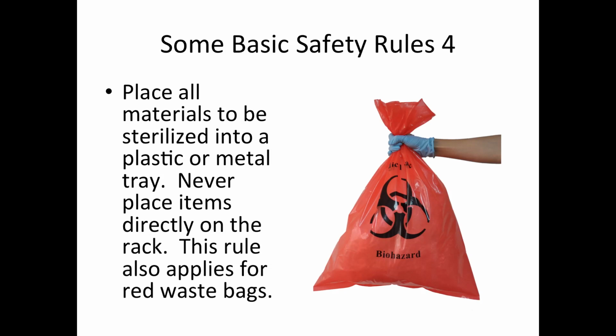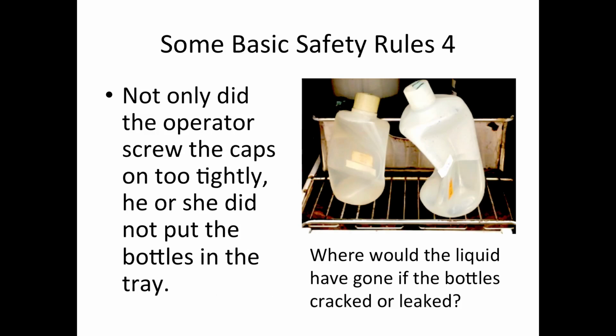You want to place all materials to be sterilized in a plastic or metal tray. You do not want to place them directly on the autoclave rack, and this rule also applies to the red waste bags. So let's look at this photograph here. The operator made two mistakes when loading the autoclave. First, they put the caps on too tightly. So what happened is as the liquid heated up, the steam escaped. The cap was then on very tightly, so as the autoclave cooled, there was very little pressure inside the bottle, and the atmospheric pressure started crushing the bottle. Secondly, where would the liquid have gone if the bottles had cracked or leaked? You'll notice that they're directly on the autoclave shelf, and if they had spilled or cracked, the contents would have fallen into the sterilization chamber.